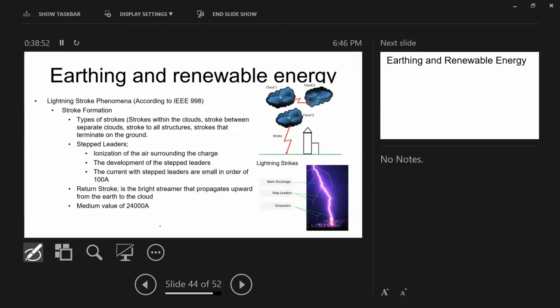If you have a conductor, what's jωL? So you no longer have a resistance; you have something called surge impedance. Don't tell me that when lightning hits a transmission line, it will go through the wire. It will go to the ground, it's not going through the wire.